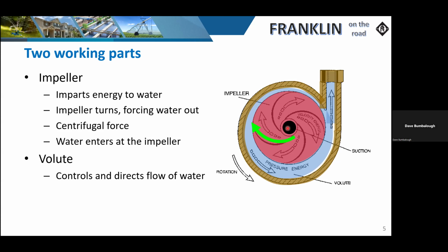Well, in the early days, that was acceptable, just due to, we knew what we had. The efficiencies on this particular pump are lower, but due to Department of Energy requirements, especially with pump manufacturers and/or motor manufacturers, that bar has been raised. So we as a manufacturer, along with others that are out there, have to improve our pump efficiencies. In the early days, where that wasn't as strict, there was a little bit of recirculation, which was okay. The tolerances weren't as tight. So if we were to pick up any particulates, like a little bit of sand or debris while pumping, it was usually easy enough to be passed through and pushed on out the end of the pump.